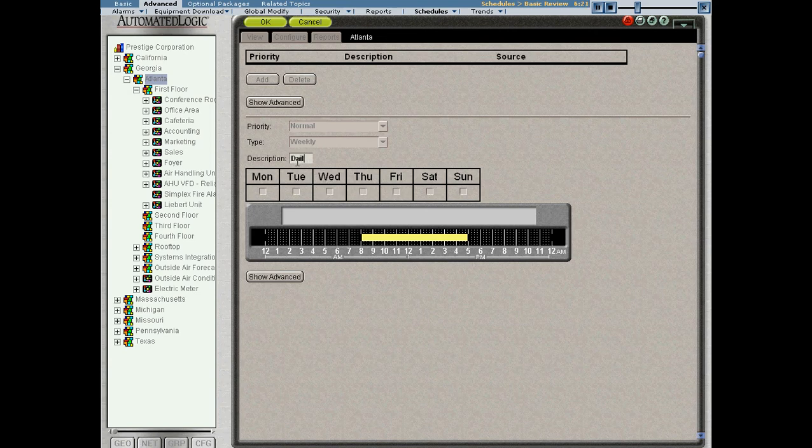And this is very powerful because by simply making one quick schedule, Monday through Friday, and downloading the entire building, I've essentially said, Monday through Friday, basically forever, don't worry about dates, occupy the building from 8 to 5. Now I could change the time by typing in the box, or I could left click on the actual graph and pull the bar over.